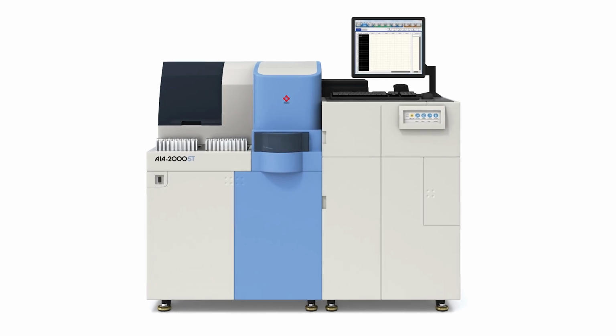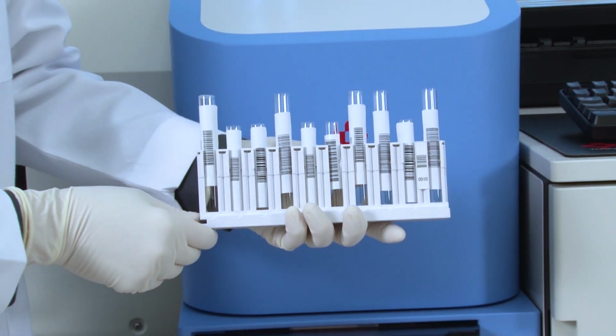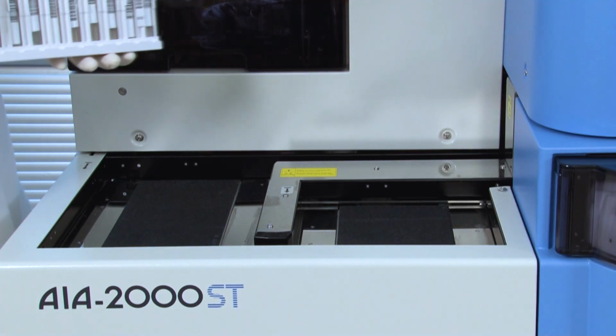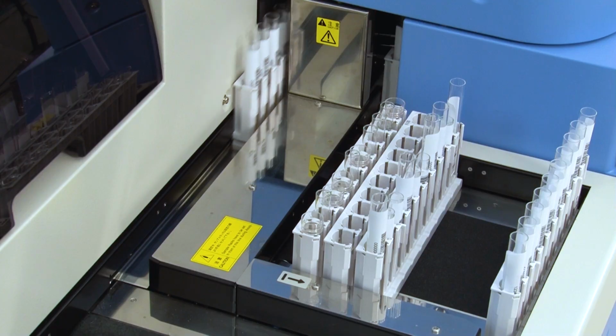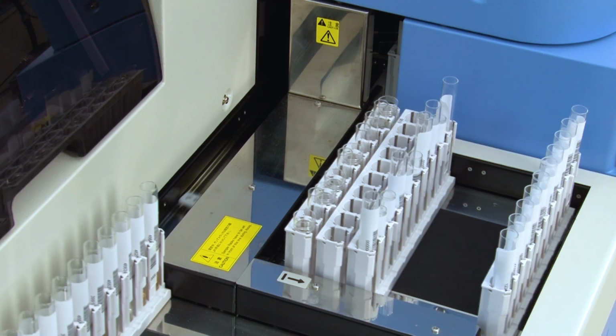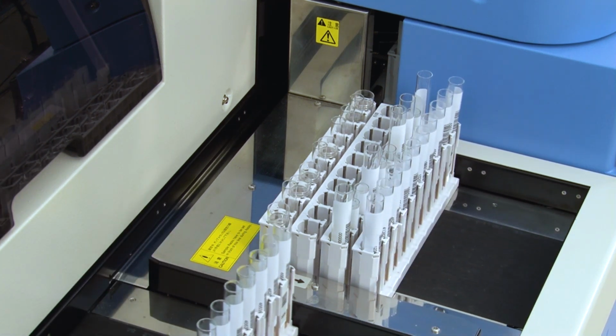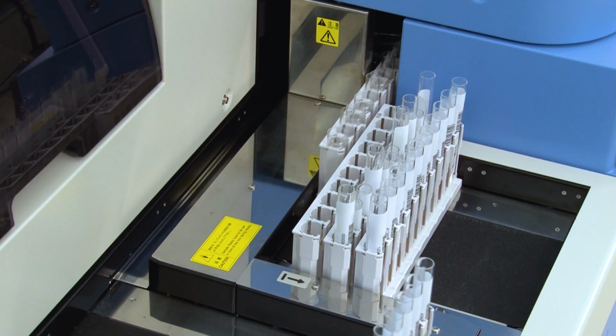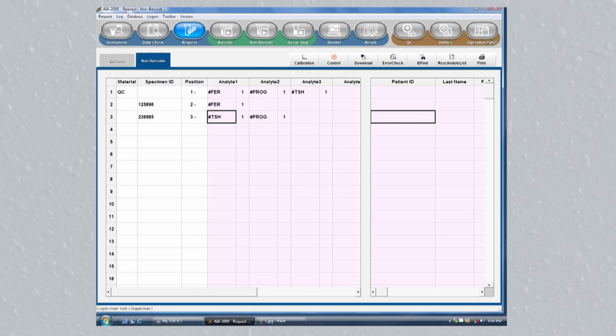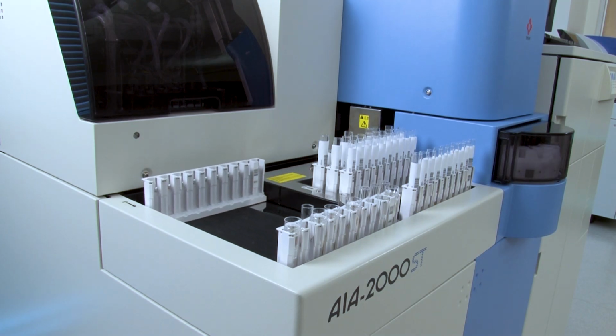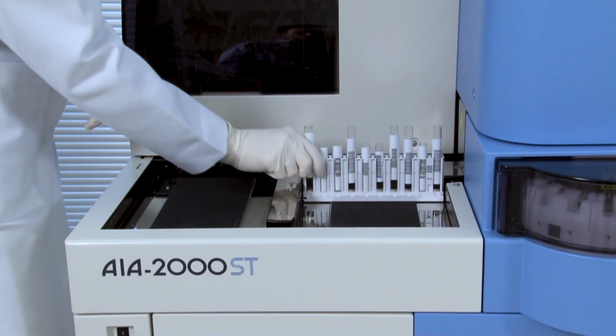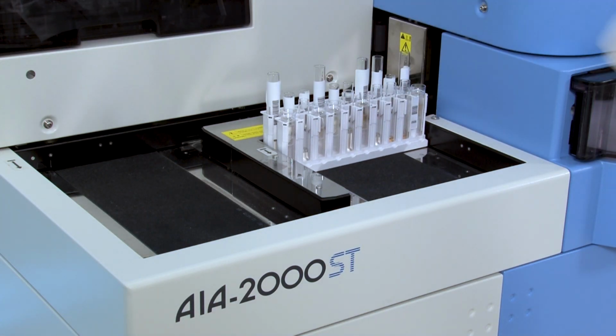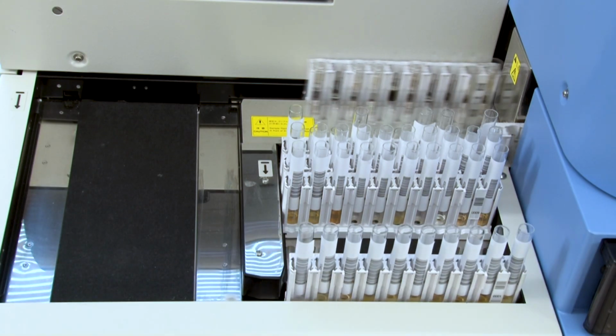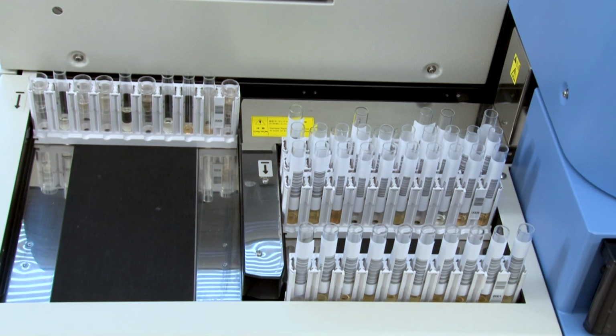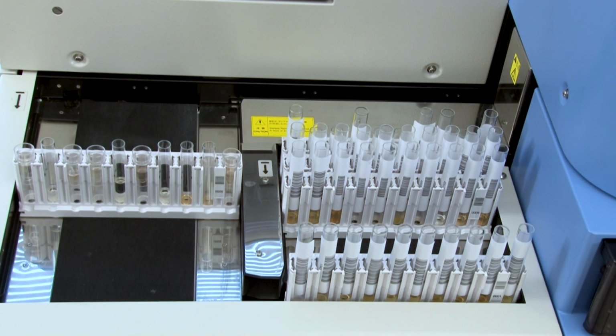To begin testing, the operator simply places barcoded primary sample tubes or sample cups into the barcoded sample racks. If the system is interfaced, the barcoded racks and tubes are read, and the requested assays are performed. For non-barcoded specimens, the operator merely types in the sample ID, and the instrument does the rest. Barcoded and non-barcoded samples can be placed randomly in the racks and will be assayed according to the work list. With continuous loading and random access operation, additional samples and tests can be added at any time without interrupting sample processing.